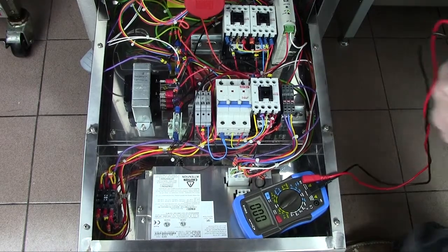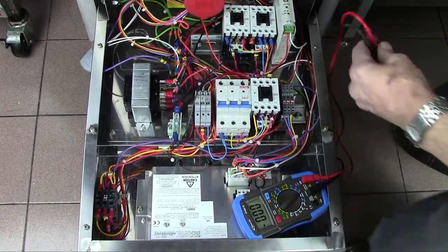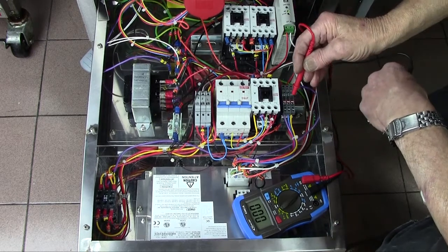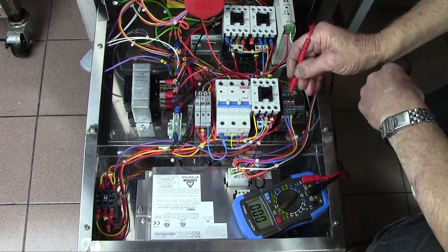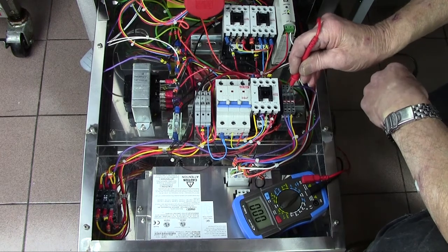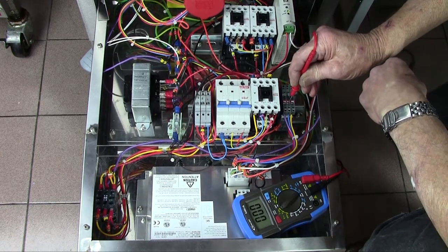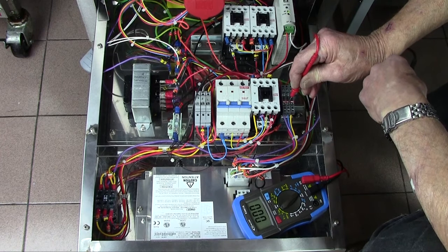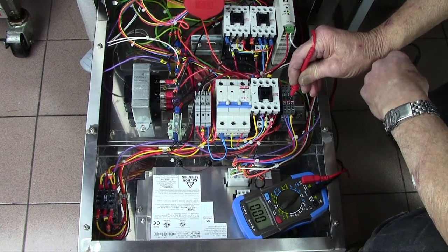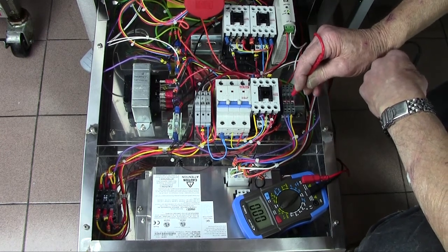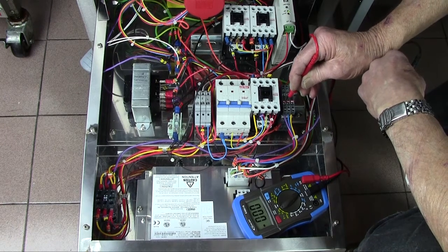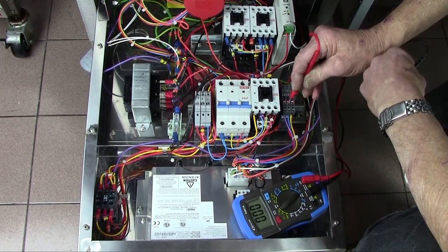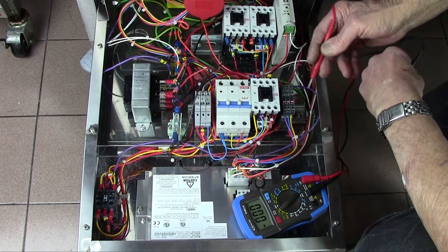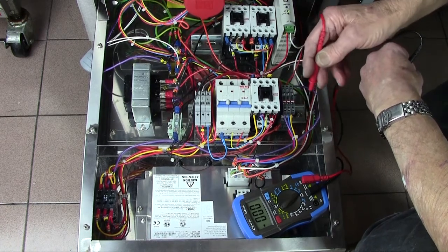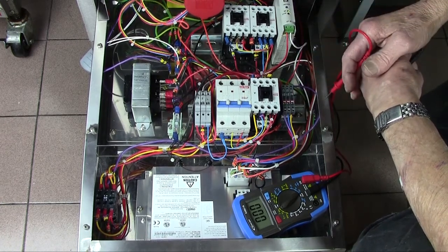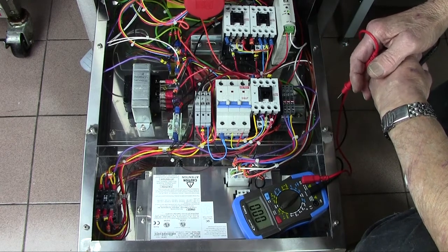If top is high, check that the relay 2, which has a very small light that you can't see on camera, but from directly above there's a green light that indicates whether the relay is activating or not. At the moment, both relays are deactivated while the machine pulses. Wait until it comes on again. If the lights are on, check the voltage to make sure that the relay is activating.